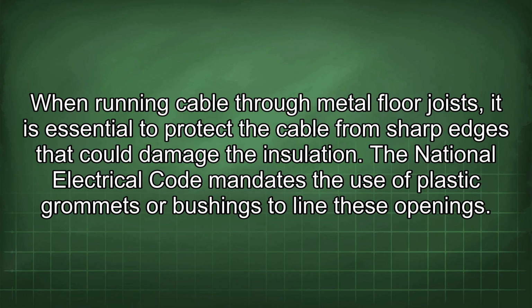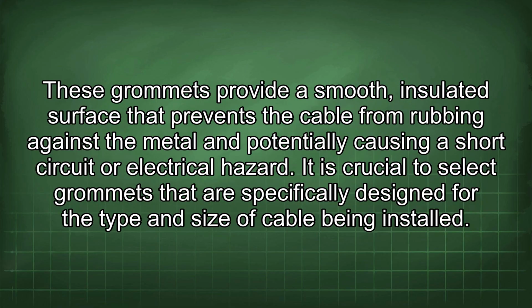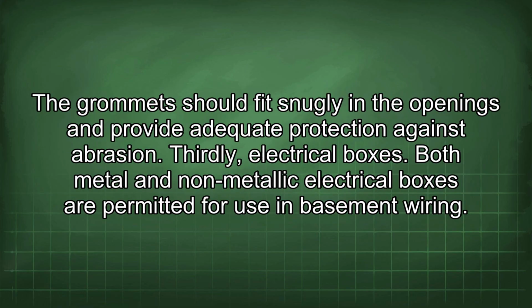The National Electrical Code mandates the use of plastic grommets or bushings to line these openings. These grommets provide a smooth, insulated surface that prevents the cable from rubbing against the metal and potentially causing a short circuit or electrical hazard. It is crucial to select grommets that are specifically designed for the type and size of cable being installed. The grommet should fit snugly in the openings and provide adequate protection against abrasion.